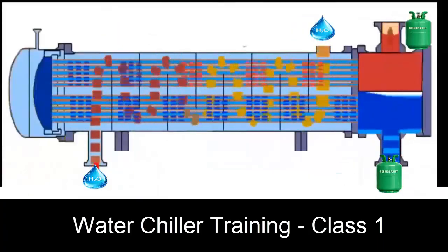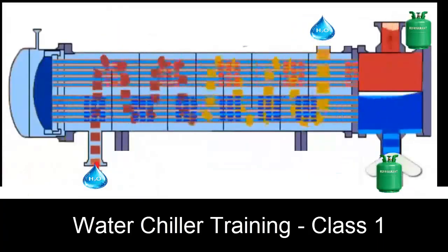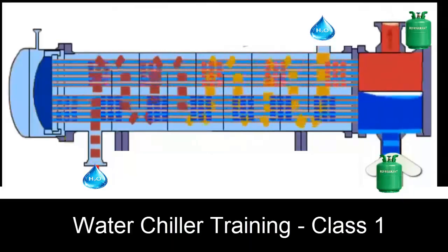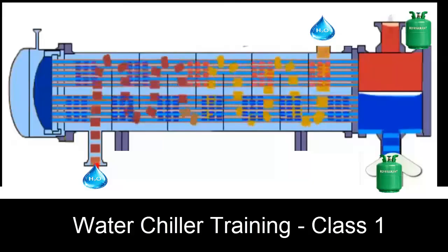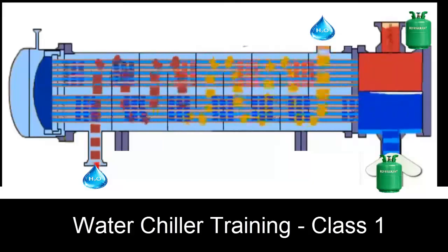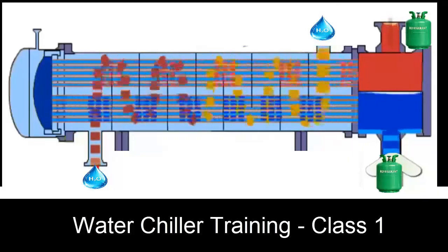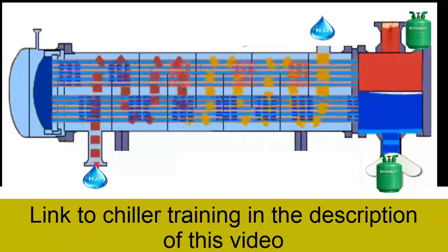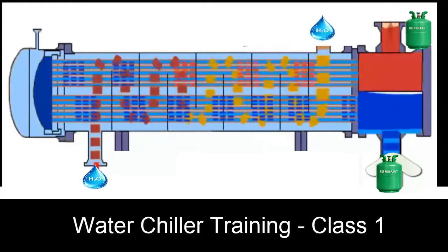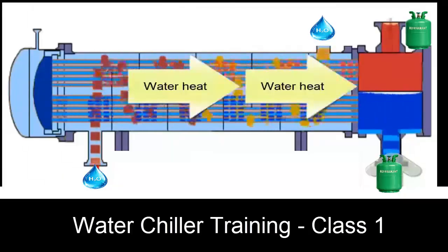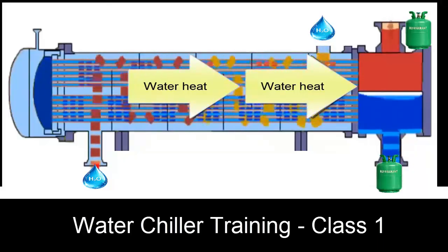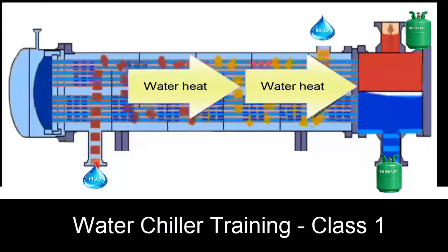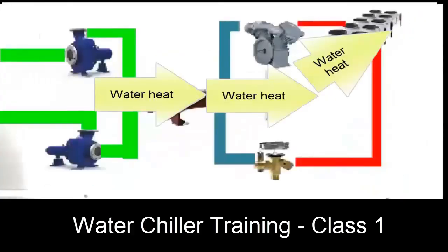This heat exchange happens inside the casing called the cooler. Inside the cooler, we have the evaporator of the refrigeration circuit and the pipes carrying the water that needs to be cooled. What happens is the following. The water enters the chiller at a higher temperature through the primary pump and reaches the cooler. Through thermal communication, not physical contact, the cold refrigerant absorbs heat from the water. The refrigerant, having a lower temperature, cools the water because heat naturally flows from the warmer circuit to the colder one. This transfer of heat from the water loop to the refrigeration loop is what allows the generation of chilled water.